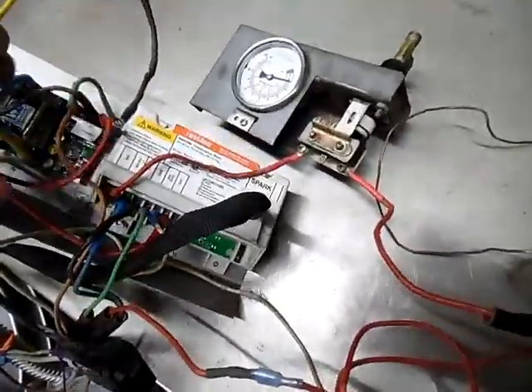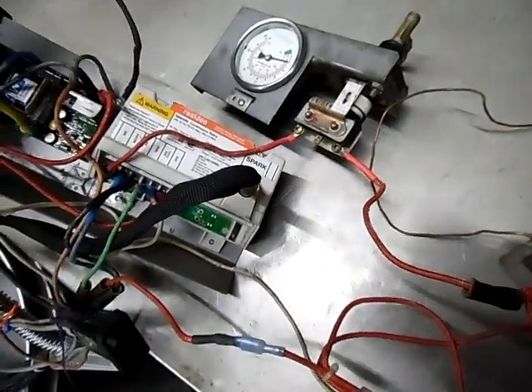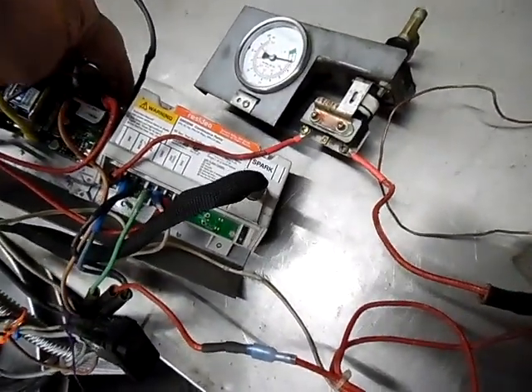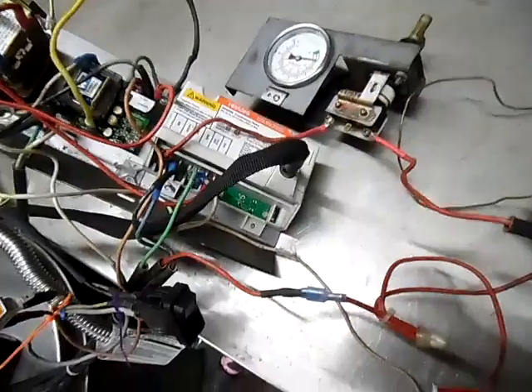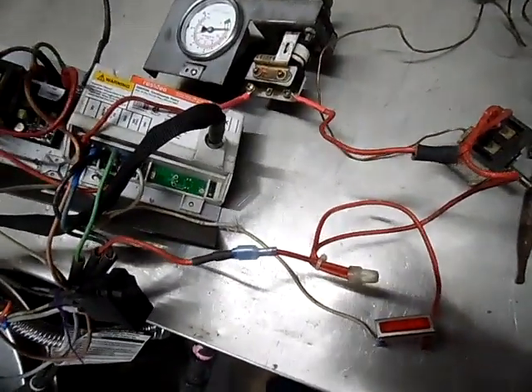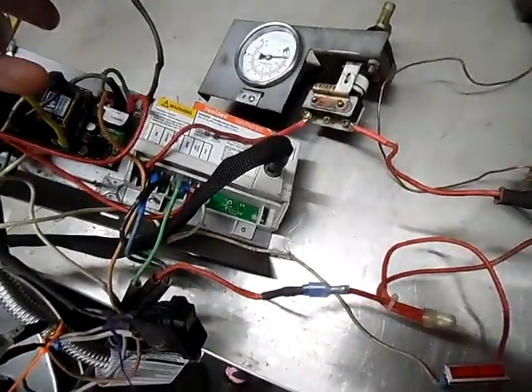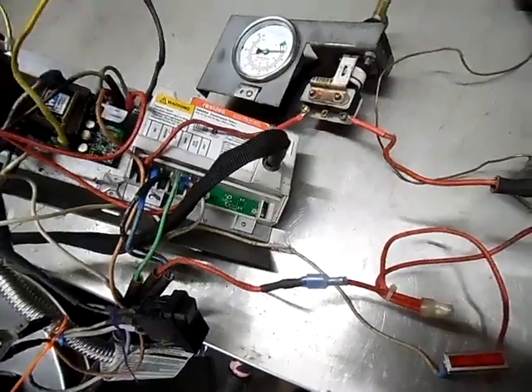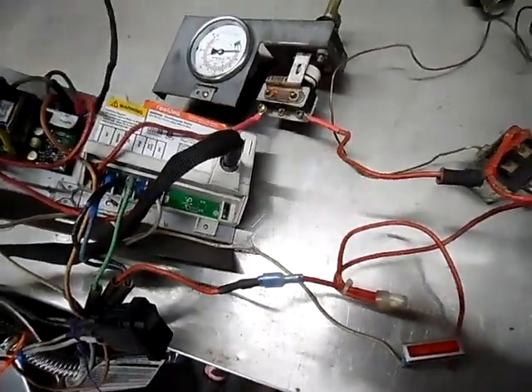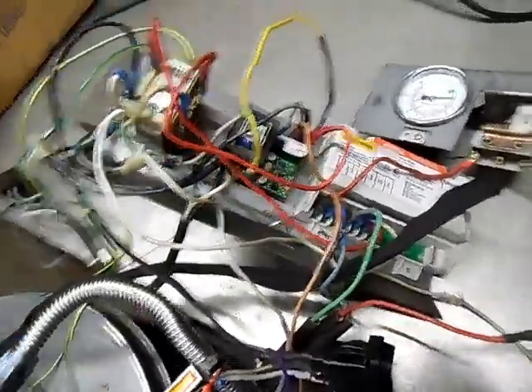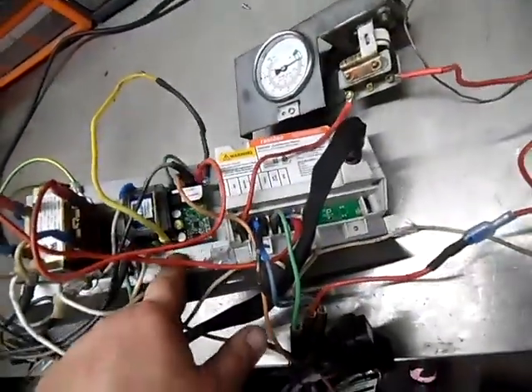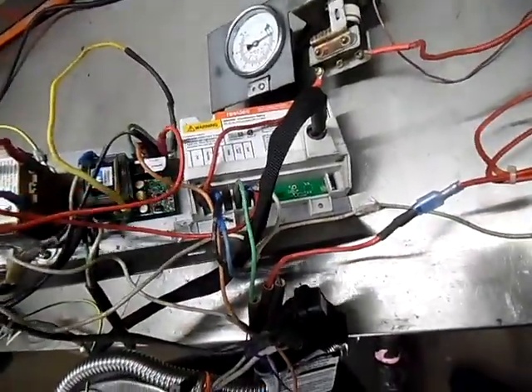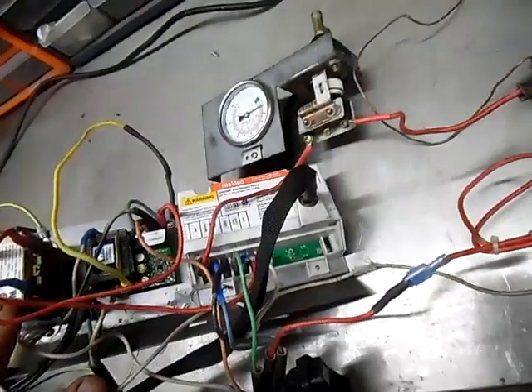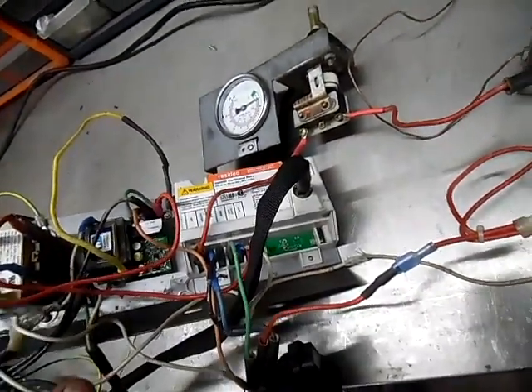Same way you can test your water sensor, if it's dirty or not. Many times it's just very dirty, you've got to clean it. But here in this case, you could ground your terminal. If everything's working fine but your water board won't trip off, you can ground your probe. If that's working, your water board comes on, and then you replace your water probe. Now in this case, once that's satisfied, your transformer powers up, and then we get the 24 volt side of this.